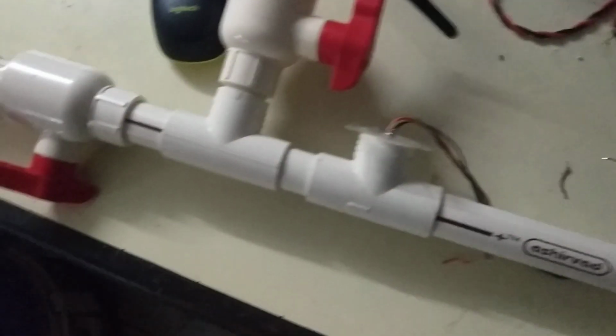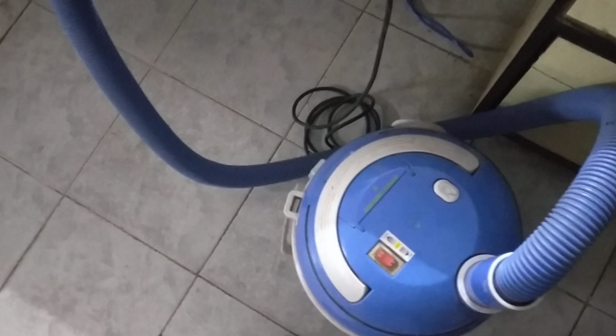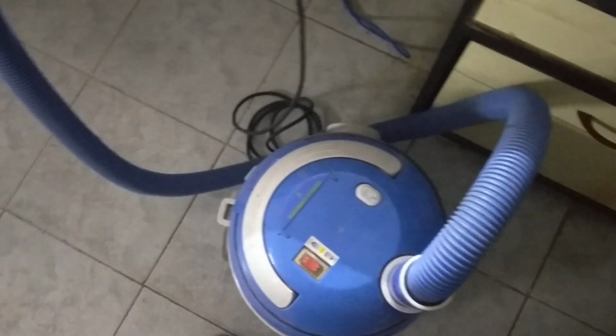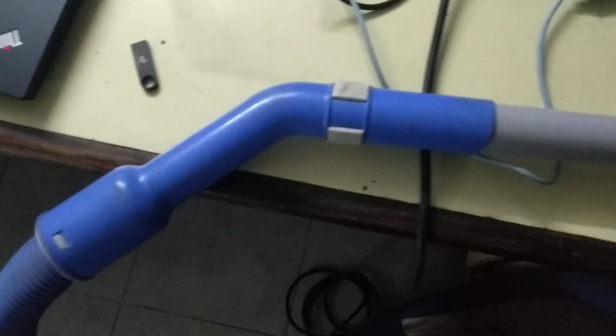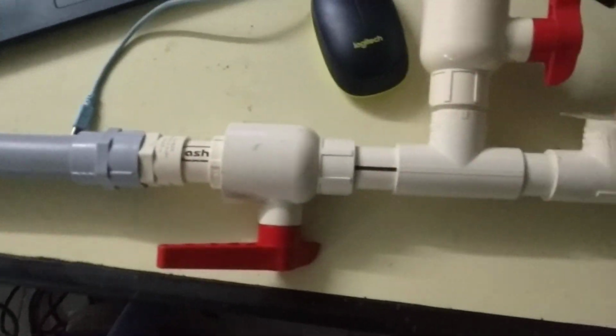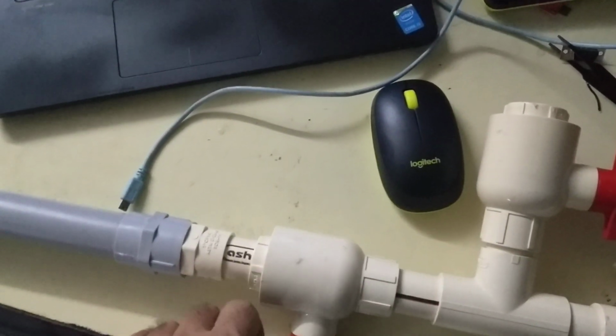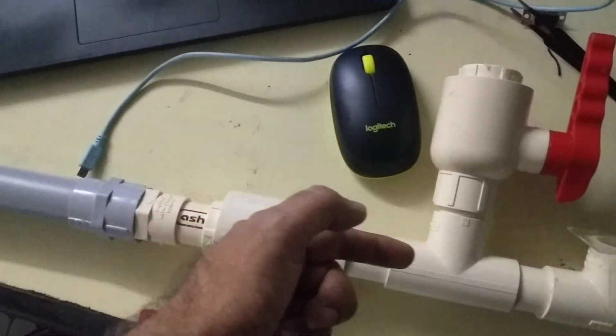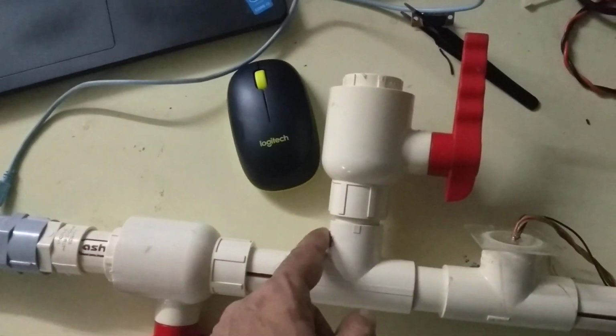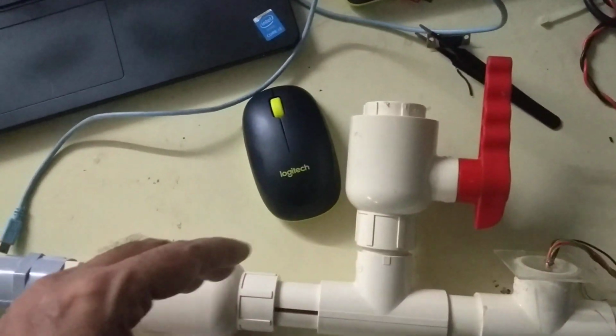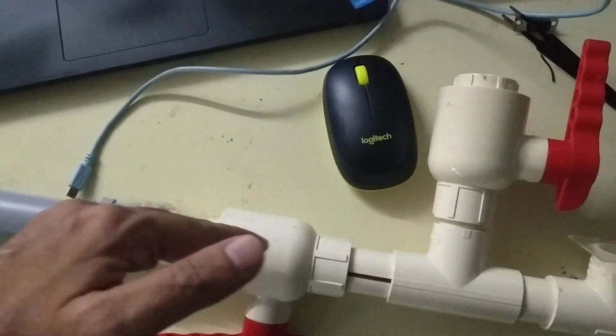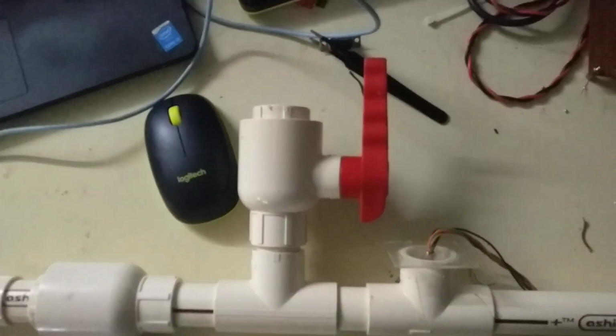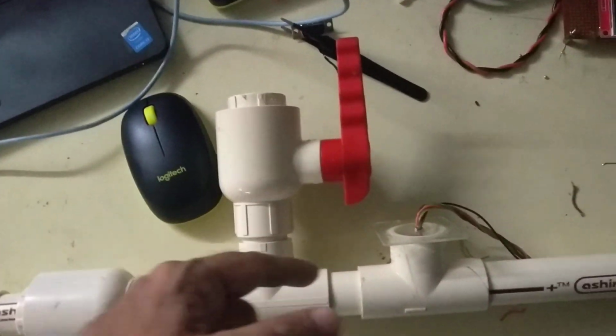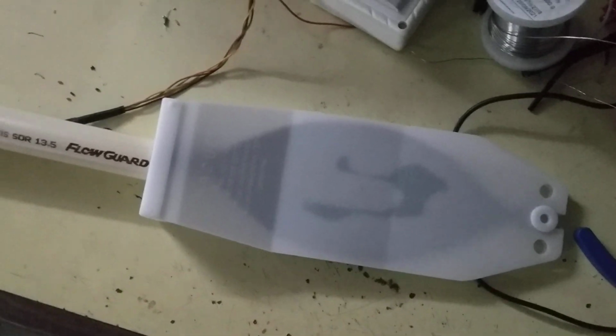So it begins with my vacuum cleaner here. It's an extremely noisy vacuum cleaner, and I have connected it to a plumbing pipe which has two valves. One valve regulates how much air will flow in, and the other is a let-off valve. So what happens is that when very high pressure air is coming this way and going all the way here, in spite of the leak here, the pressure is pretty substantial over this test lung, and this is a standard test lung. It's a 1 liter capacity test lung.